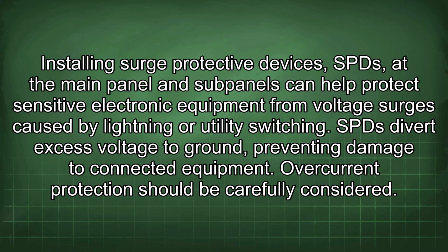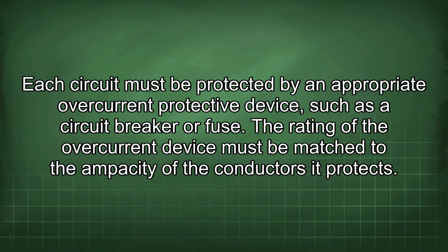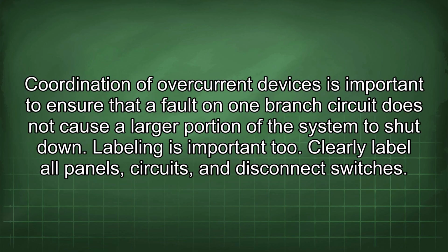Overcurrent protection should be carefully considered. Each circuit must be protected by an appropriate overcurrent protective device, such as a circuit breaker or fuse. The rating of the overcurrent device must be matched to the ampacity of the conductors it protects. Coordination of overcurrent devices is important to ensure that a fault on one branch circuit does not cause a larger portion of the system to shut down.